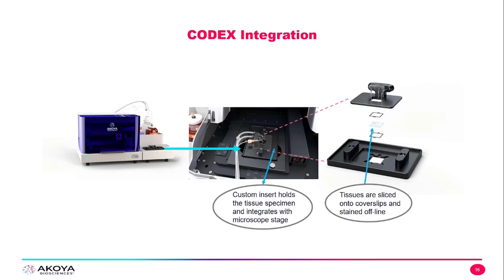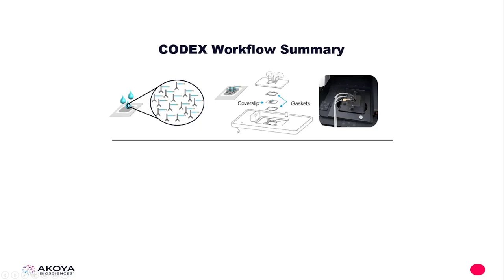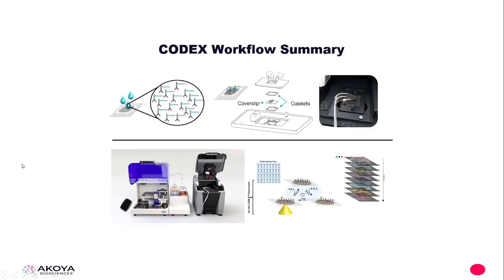Let's see the entire workflow in a single slide. We section our tissue and stain it with a cocktail of oligo barcoded antibodies. We then put our cover slip in a CODEX insert and place that on the microscope stage. The fluidic lines go to the CODEX insert, and all of the reveal, image, and repeat steps happen online while the insert is on the microscope stage. The only manual step in this whole process is really the staining of that cover slip — all other reveal, image, and remove steps are automated by CODEX fluidics and the microscope automation.